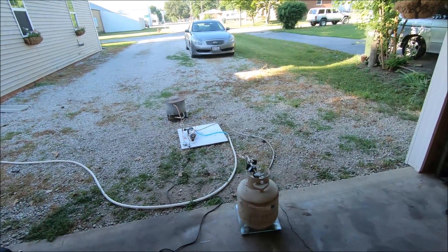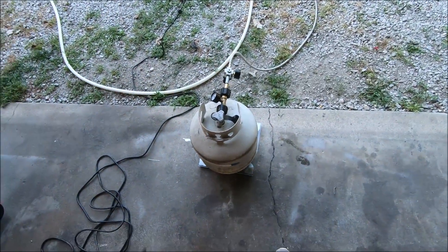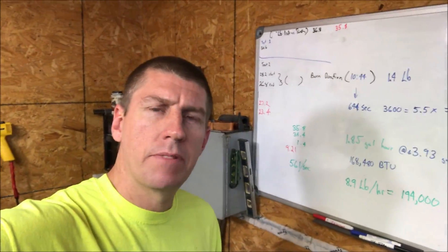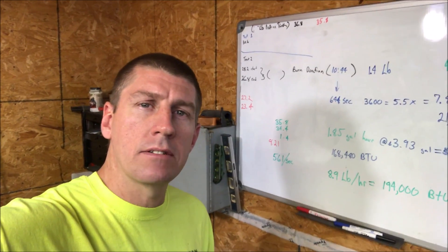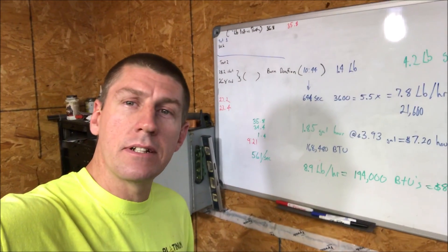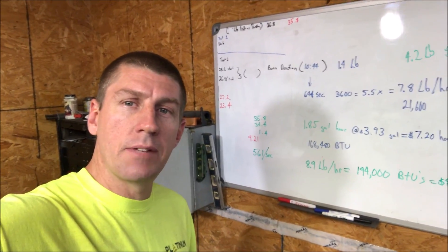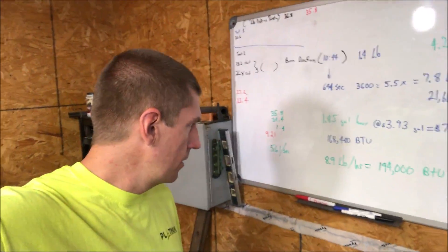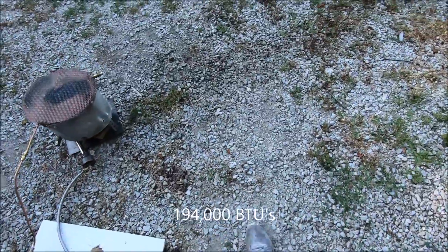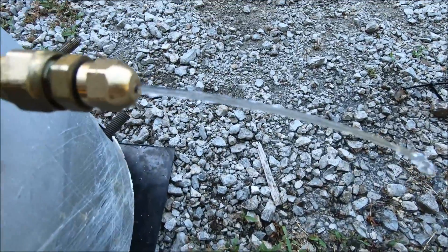In this video we've got two things going on. I'm going to try and zero in on the actual output rating of this burner. Based on the calculations we have about 194,000 BTUs to work with, coming out to about $8.33 an hour to run this. We're producing 270-degree steam, verified by weighing the tank before and after, and we're going to be trying a nozzle on this 40-foot coil to see what happens.